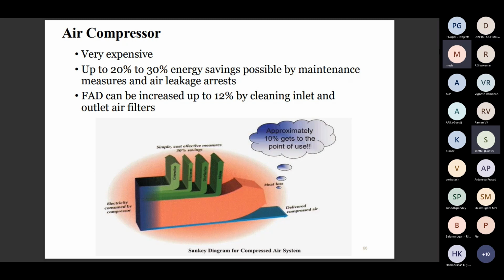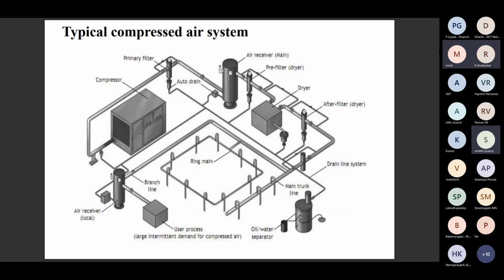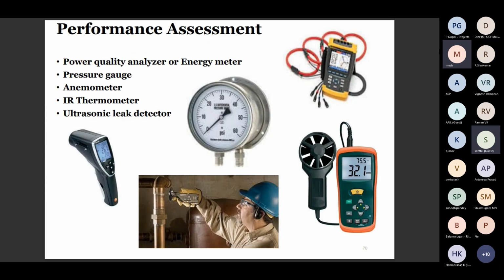Next one. So this is the recommended typical ring main system layout for the compressed air system. Next. Next. For performance assessment of any compressed air network, these are the instruments we need: a power quality analyzer or energy meter for noting the unit consumption, and pressure gauges, anemometer, IR thermometer, and ultrasonic leak detector. This leak detector helps us quantify the leakage quantity.